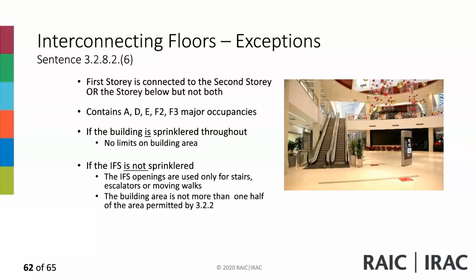So it is sprinkled throughout, or where the building area is not more than 1/2 of the area permitted by section 322, the openings through the floor are used only for stairways, escalators, and moving walks. And there is a note in the appendix related to that.